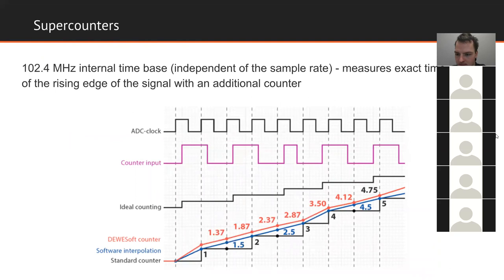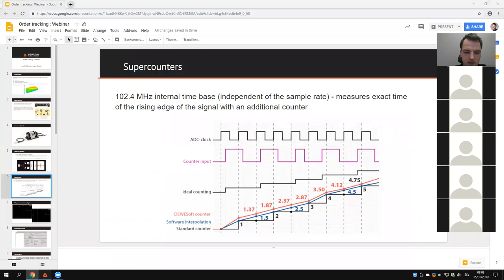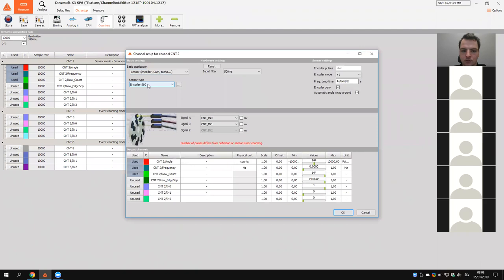We can measure angle very precisely with our super counters. What super counter means is that we have an internal time base of 102.4 MHz, which measures the exact time of the rising edge of the signal with an additional counter. To show this in practice, I have an encoder with 360 pulses per revolution connected to my SIRIUS.